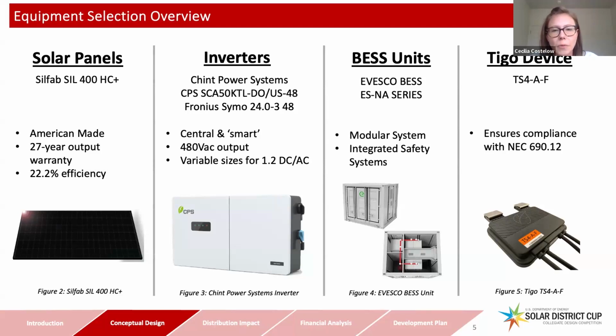For our BESS units, we went with Evesco because they have a modular design, allowing us to get really close to our optimized battery sizing from our REOPT simulations. In order to comply with NEC 690.12, the rapid shutdown requirement, we're going to install a Tigo TS4AF on the back of every solar panel module. This power electronic device will drop the voltage of each panel to 0.6 volts in the event of an emergency.